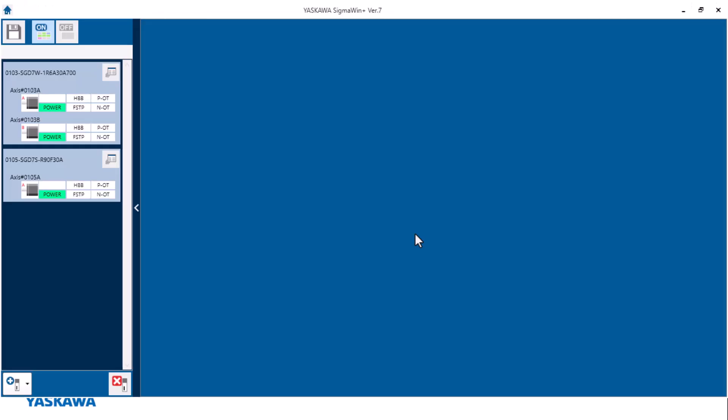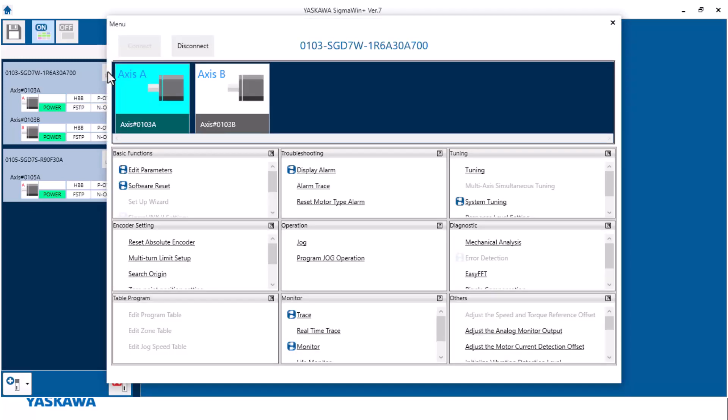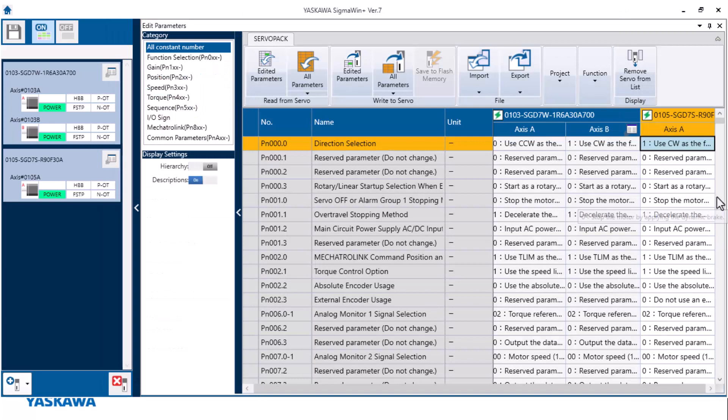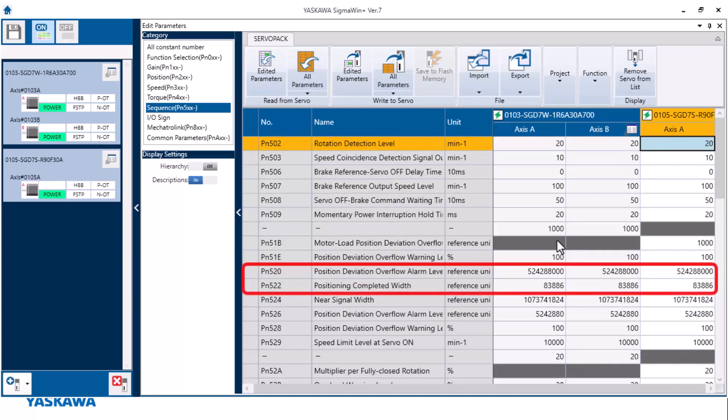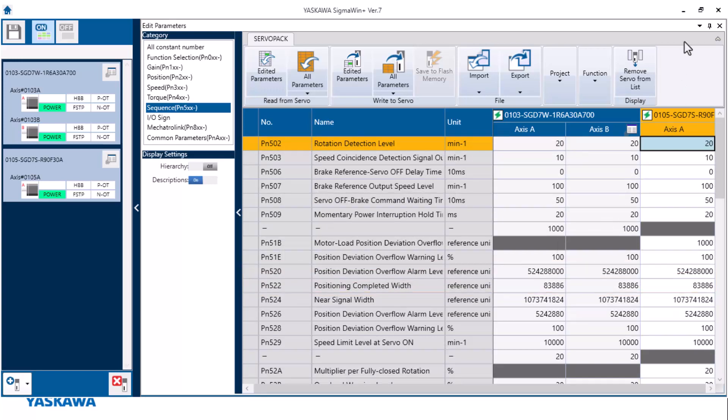While that's rebooting, I can go into SigmaWin+ and modify some extra parameters. Inside SigmaWin+, I'm going to look at the parameters. The first parameter I want to look at is PN10C. I can see that my master axis — axis A — is set to 200, and my prime axis, which is my slave axis, is already set to zero. I've also already set up PN520 and PN522. Now I want to take a basic trace just to see where the two motors are functioning right now when it comes to tuning.